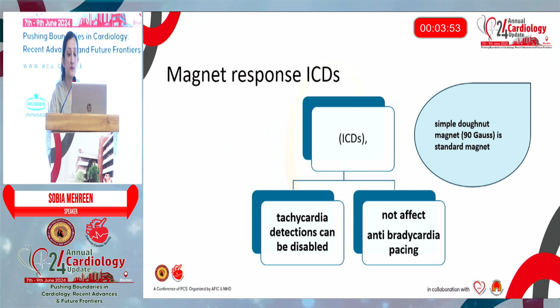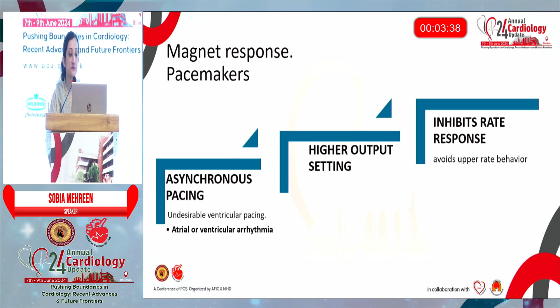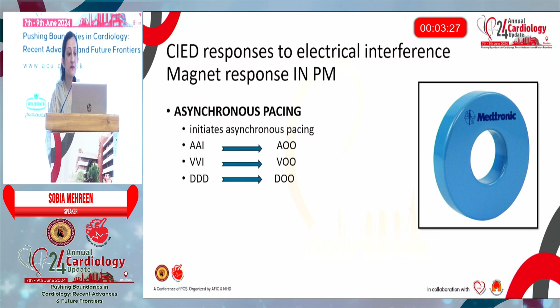The magnet response in pacemakers is different. It causes the pacemaker to switch to asynchronous pacing mode at higher pacing output, and it inhibits the rate response in the pacemakers. The asynchronous pacing mode depends on the pre-programmed pacing mode of the pacemaker. If the patient was pacing with AAI, it is switched to AOO, VVI is switched to VOO, and DDD is switched to DOO.